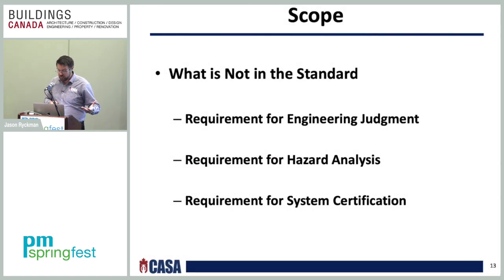Also, what's not in the standard? It is important to note that the scope of the inspection and testing is not for the technician to provide engineering judgment as to the system's design, only to determine that the system is functioning. It is similarly not the job of the technician, whoever is inspecting, to determine if the hazard classification within the building is within the design parameters of the system. That requires a judgment that is left up to the engineer or the authority having jurisdiction, okay?